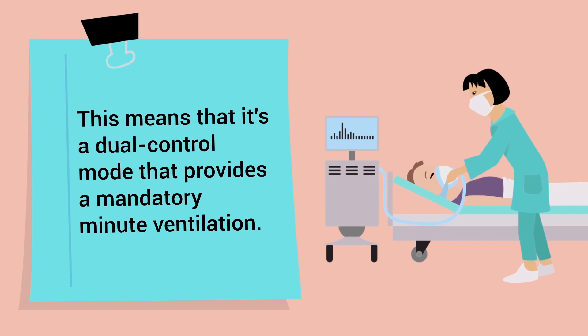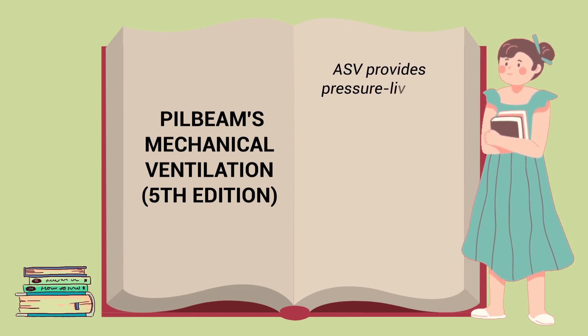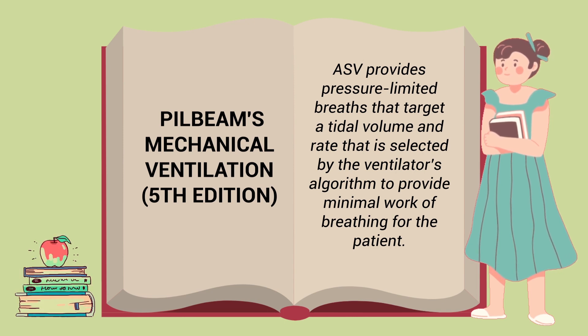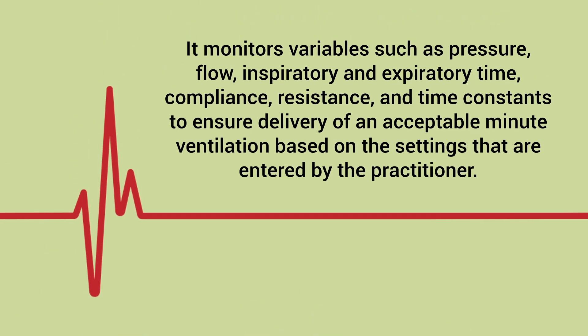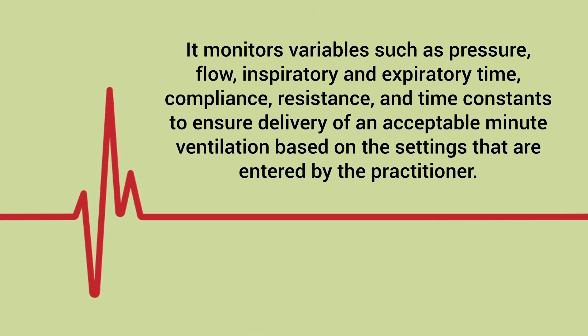ASV is a dual control mode that provides a mandatory minute ventilation. According to Pilbeam's Mechanical Ventilation, fifth edition, ASV provides pressure-limited breaths that target a tidal volume and rate selected by the ventilator's algorithm to provide minimal work of breathing for the patient. It monitors variables such as pressure, flow, inspiratory and expiratory time, compliance, resistance, and time constants to ensure delivery of an acceptable minute ventilation based on the settings entered by the practitioner.